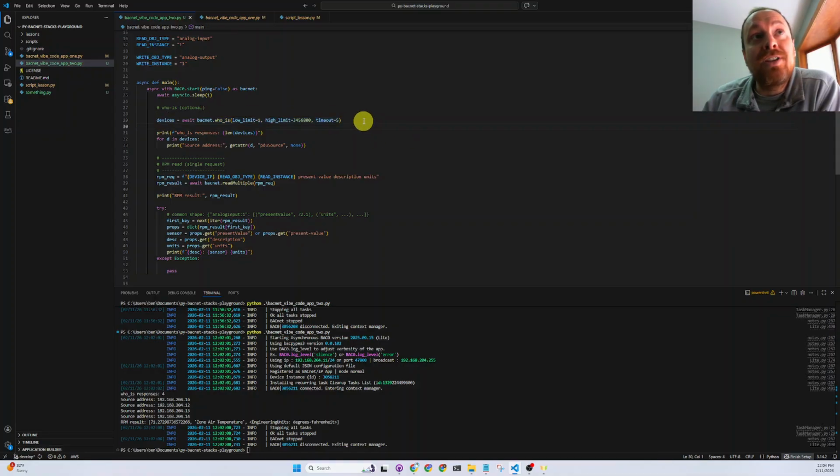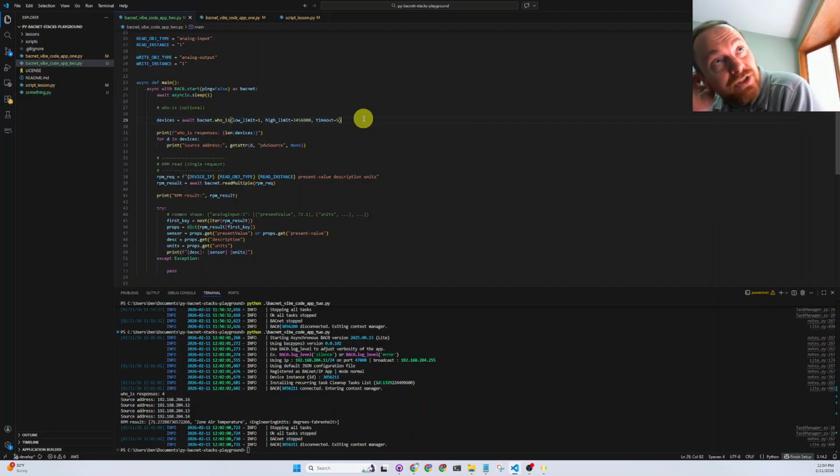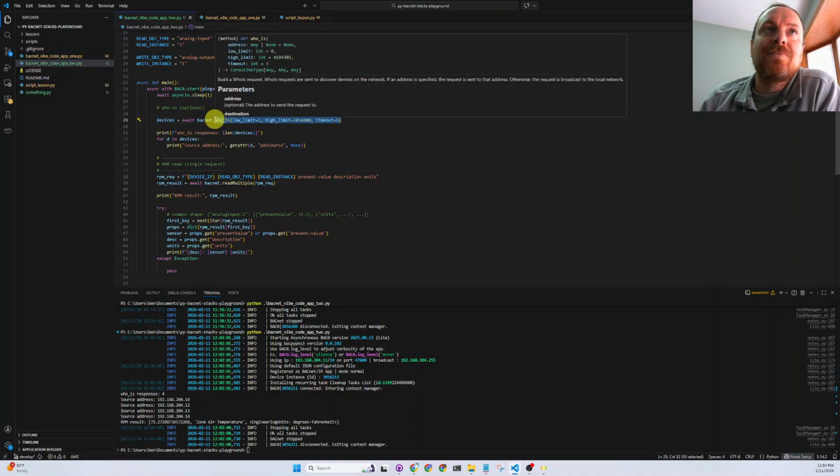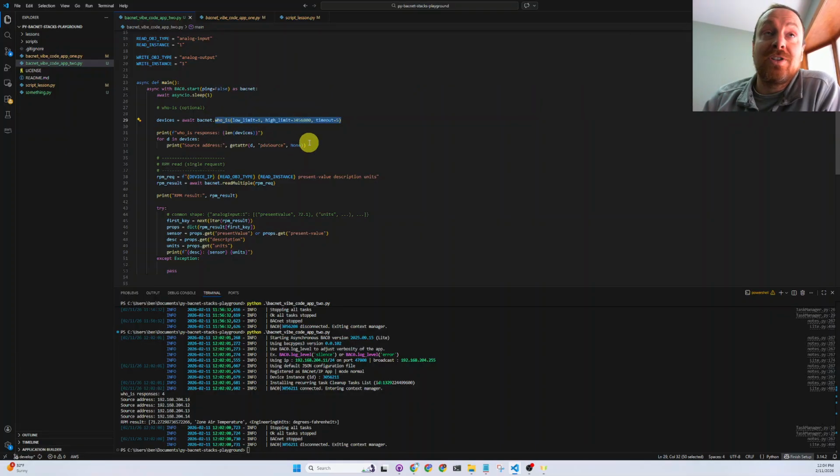And same thing in IoT. Once you discover all of your devices through a global BACnet whois, you really don't need to do this command anymore, and you shouldn't either, because it's a global request where every device stops what it's doing and responds to the whois.